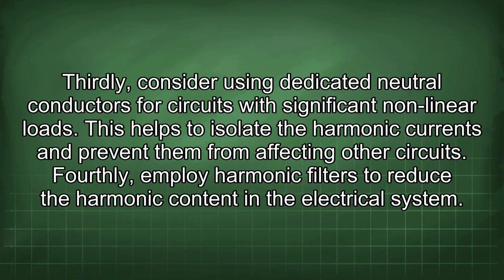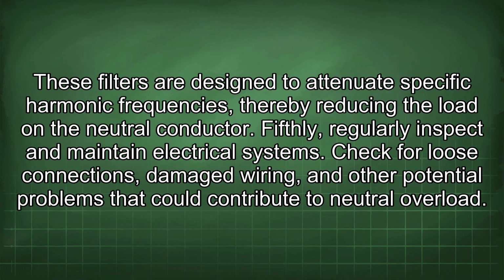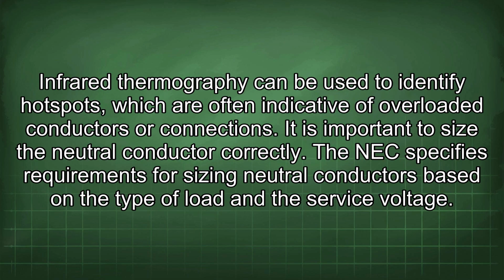Fourthly, employ harmonic filters to reduce the harmonic content in the electrical system. These filters are designed to attenuate specific harmonic frequencies, thereby reducing the load on the neutral conductor. Fifthly, regularly inspect and maintain electrical systems. Check for loose connections, damaged wiring, and other potential problems that could contribute to neutral overload. Infrared thermography can be used to identify hotspots, which are often indicative of overloaded conductors or connections.